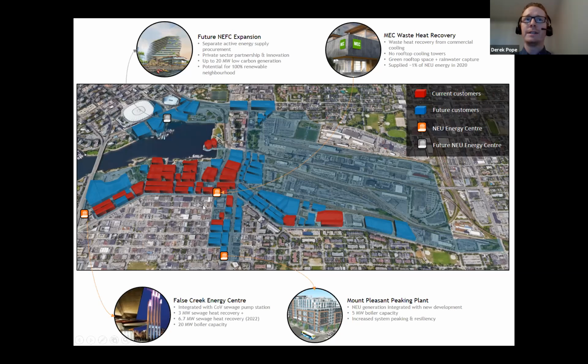The third thing on here is we do have one building where we are recovering heat from the building's cooling system. So in the summertime, when the building's in cooling mode, instead of all that waste heat being rejected to a cooling tower, the building instead runs it through a heat recovery chiller that can then reject that thermal energy into our thermal grid.